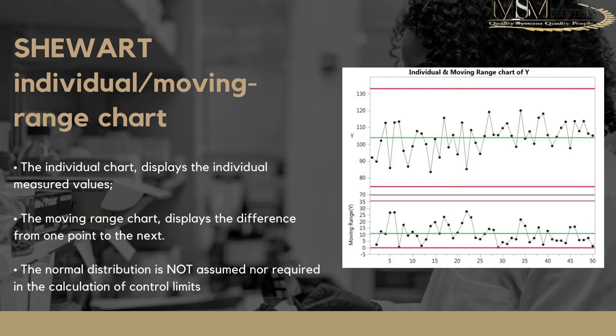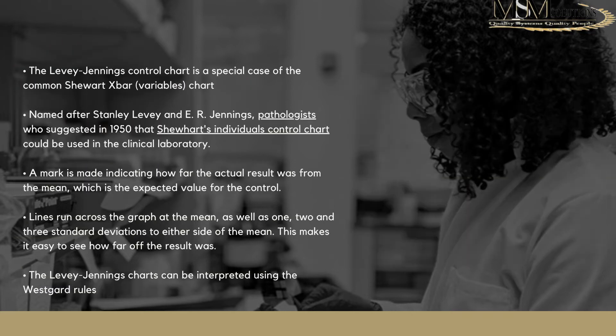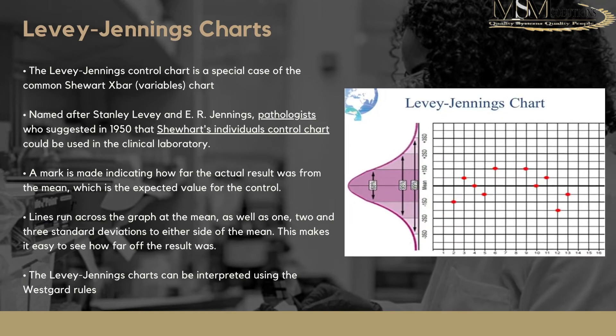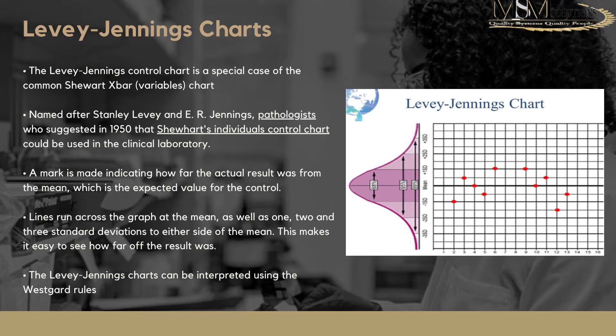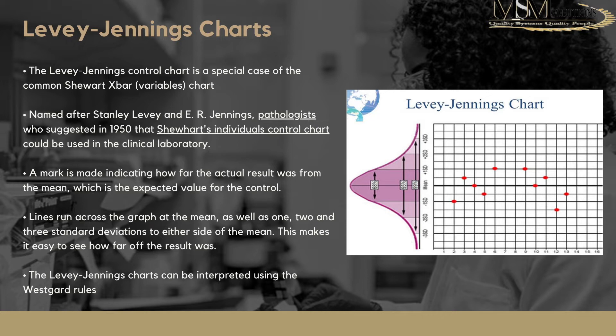In the lab we talk mainly of Levy-Jennings charts. These are a special case of the common Shewhart X chart, developed by two pathologists using these graphs in a clinical study. You have a mark representing your mean — your expected result — and then you plot different QC values every day over time relative to that mean. You also have lines for one, two, or even three standard deviations, so as you plot values you can see how far they are from the mean.